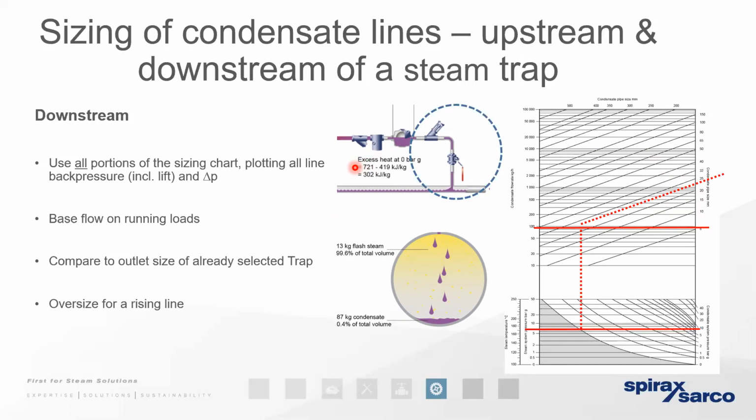And what you'll remember from the presentation we went through 2 weeks ago is that we need a pressure drop across the trap. We need to use the steam pressure to push the condensate away. So that pressure drop is a good thing because it ensures that we've got motive energy in the condensate. But the problem that causes is if we get a falling pressure behind the trap, the example we've got here, again, it's an extreme. We've got a pressure drop down to atmospheric, 0 bar gauge.